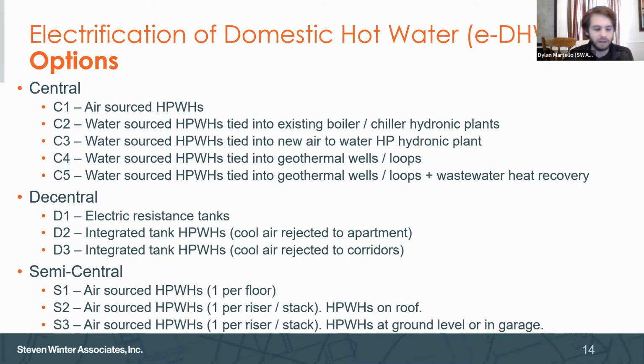And then in the apartments for space heating, you'll have a water source heat pump that's providing space heating to each apartment. So when you have that hydronic loop, you're also now able to utilize a heat pump to, again, take heat from that loop and produce domestic hot water for the building. So you can do that with a centralized system. There are a lot of heat pumps in that system, and that's described as a challenge. But I think this is where the creativity comes into play, and we're thinking about moving our heat and cool air and water throughout the building in creative ways to maximize efficiency. And as I'll get into in a minute, we do have a project that is actually doing this, so we'll talk about this in a second.